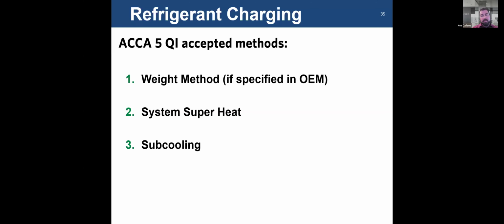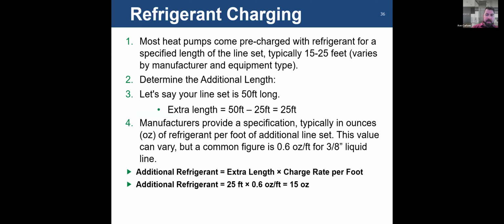They don't want you doing superheat and subcooling because of the variations in the system. Those units will maintain their own superheat and subcooling depending on the conditions. For example, we talked about heat pumps coming pre-charged for somewhere between 15 and 25 feet. That's typical, but it does vary depending on what you're working with. You'll need to determine the length of line set beyond what was included in the base charge of that unit. So, for example, you install 50 feet of line set and it comes pre-charged for 25. You need to add refrigerant. 50 minus 25, you've got 25 feet of additional line set.